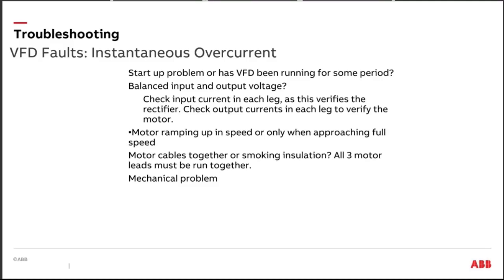Okay, you can always measure your motor current in each leg. Now, the really cool thing is with Drive Composer, you can actually connect up through the keypad. You've got a port on the keypad. You don't have to open the door of the drive for nothing. Plug your laptop up to the keypad on the door, and now I can see the motor current in each leg right there on my laptop. Okay, wicked cool.